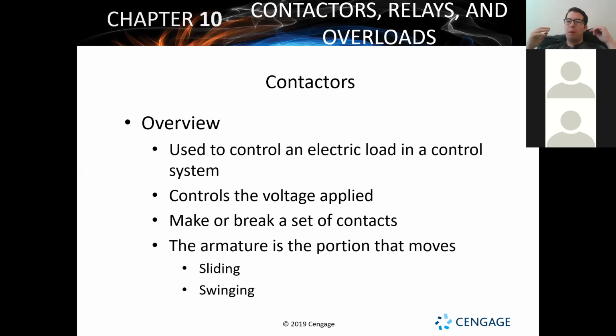Okay, so for a contactor, we test it with voltage. What we're going to see is with an open switch, you're going to read what's called source voltage. All right, so source just means, is it line voltage or is it control voltage? Whatever the source or the starting voltage for that component is. So for a switch on a wall, for a light bulb or for a ceiling fan or whatever it's going to be in a house. All the outlets in a house are 120 volts. All the switches in the walls are typically 120 volts, and that's it.